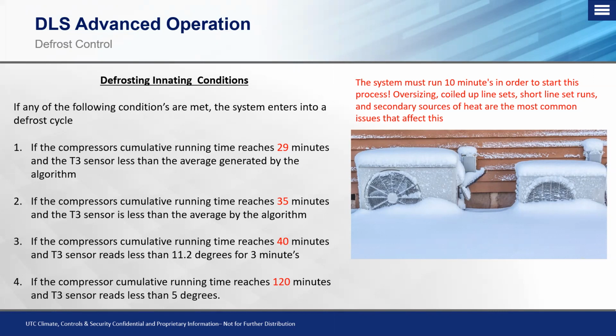So that's why it's extremely important to make sure that we're not oversizing this, we're not vertically coiling up line sets, we're meeting the minimum for line set runs, which is 10 foot, and any secondary sources of heat are set appropriately. Preferably to not have them in the room at all, but if they are, to set them back. Make sure that the ductless system is fully handling the load.